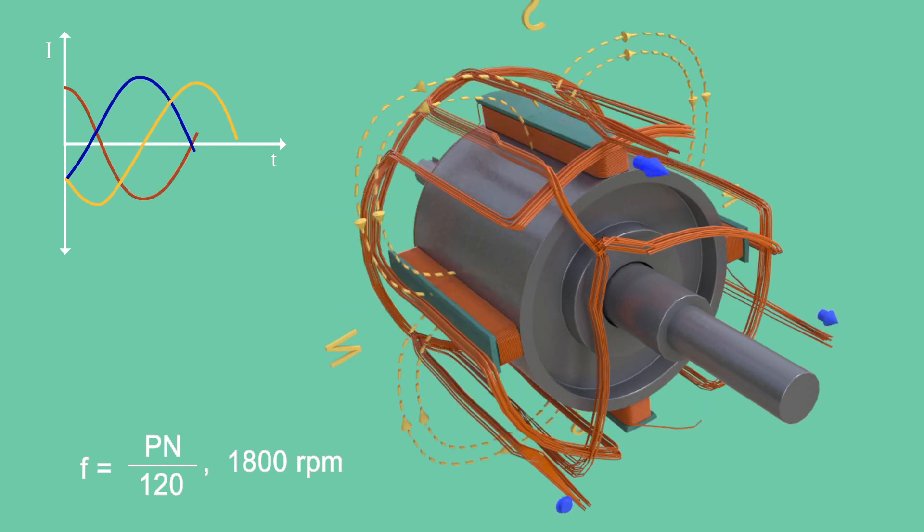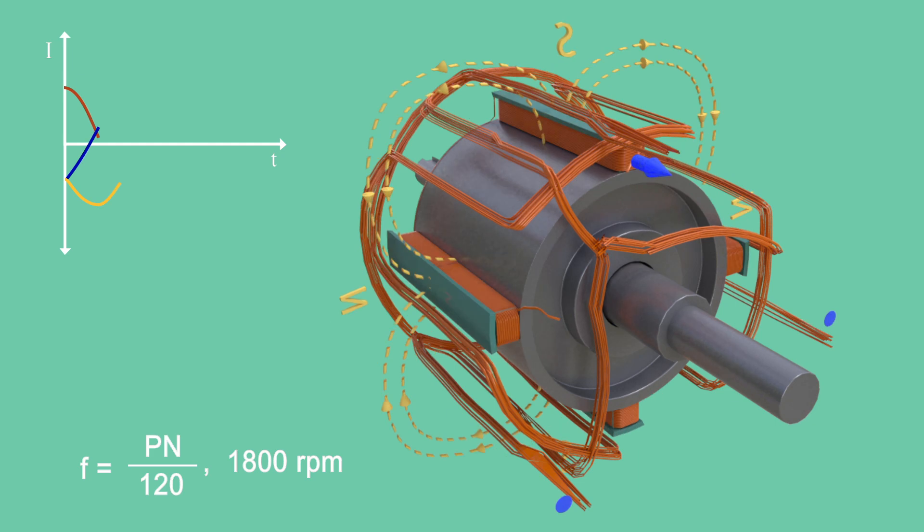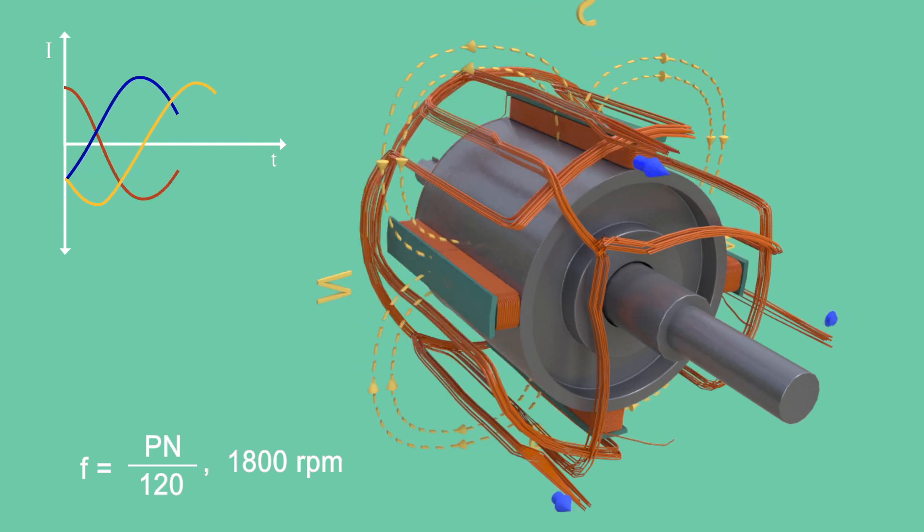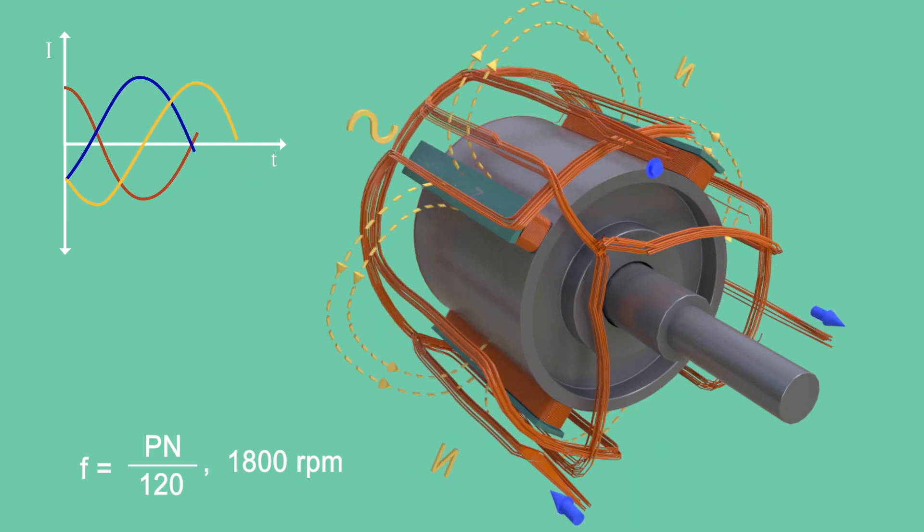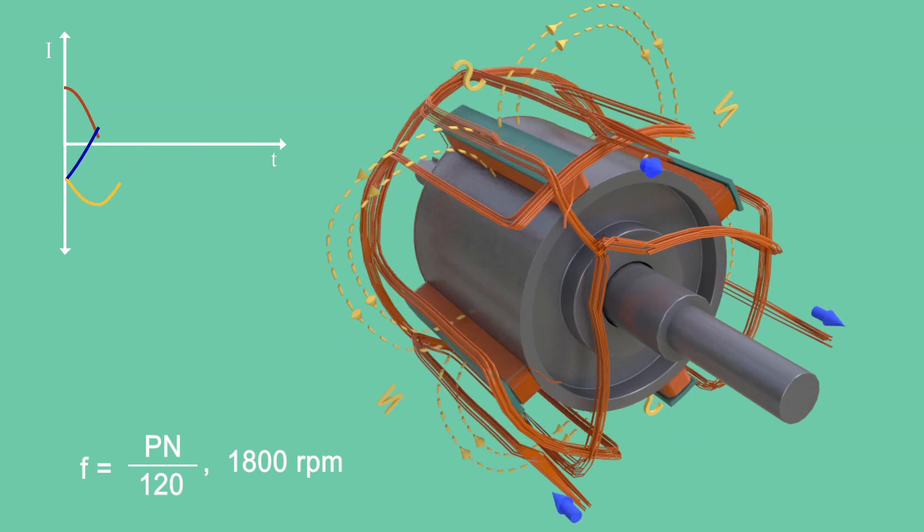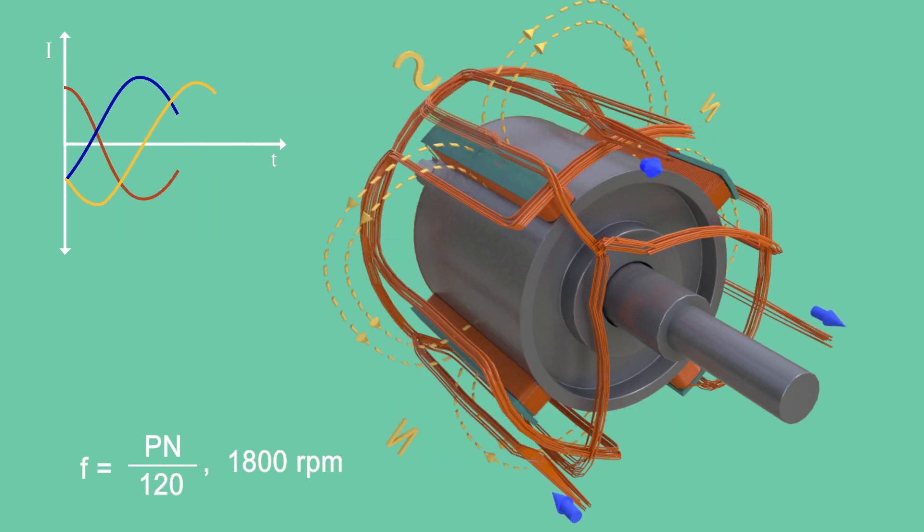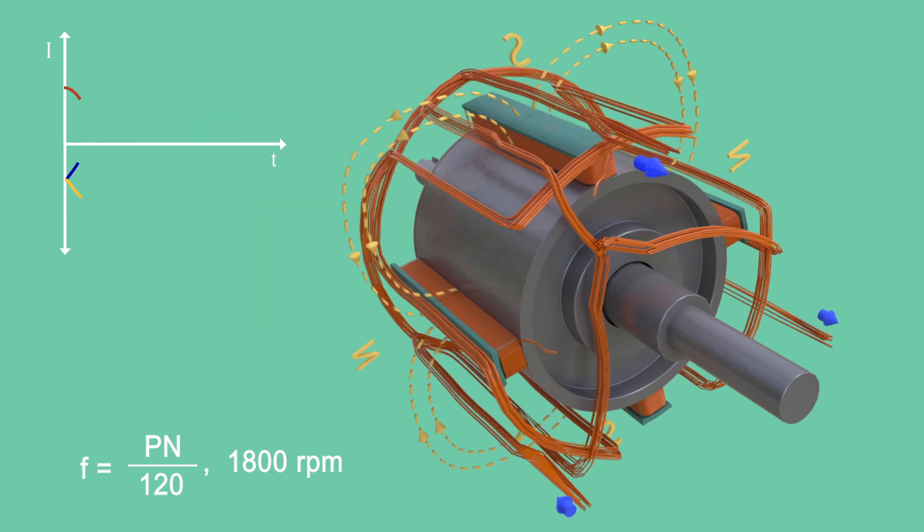So salient pole rotors generally have 10 to 40 poles, which demands lower RPM. Salient pole rotors are used when the prime mover rotates at relatively lower speeds from 120 to 400 RPM.